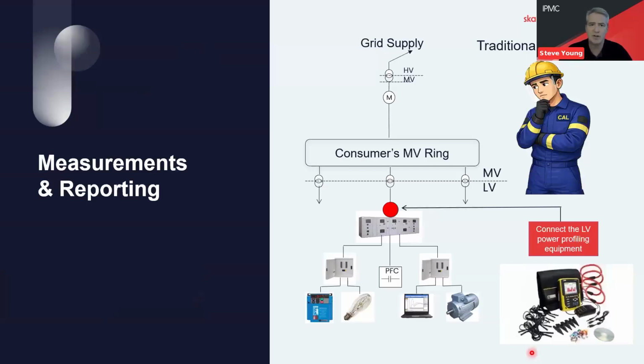So traditional monitoring, we just populate, if you like, a consumer's high voltage or medium voltage ring with 3 transformers transforming down to our usable low voltage. Typically, a portable power quality analyzer would be connected directly downstream of that transformer so that we can pick up all of the associated characteristics and values across a typical peak demand period. They're quite commonly 7 days, sometimes a little longer, depending on the specific requirements.